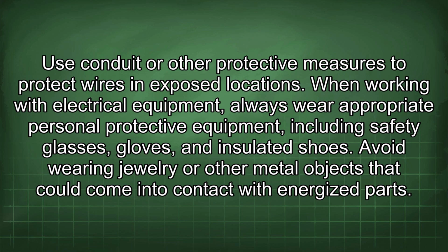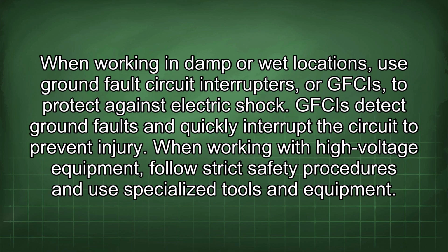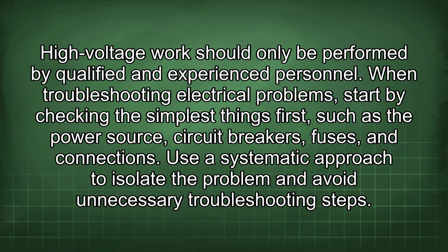When working with electrical equipment, always wear appropriate personal protective equipment, including safety glasses, gloves, and insulated shoes. Avoid wearing jewelry or other metal objects that could come into contact with energized parts. When working in damp or wet locations, use ground fault circuit interrupters, or GFCIs, to protect against electric shock. GFCIs detect ground faults and quickly interrupt the circuit to prevent injury. When working with high voltage equipment, follow strict safety procedures and use specialized tools and equipment. High voltage work should only be performed by qualified and experienced personnel.